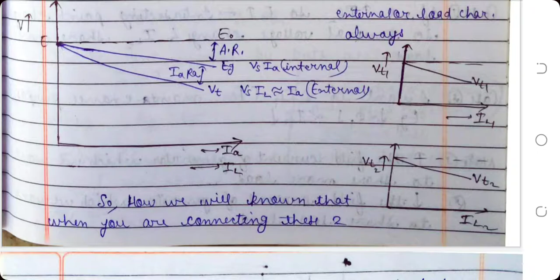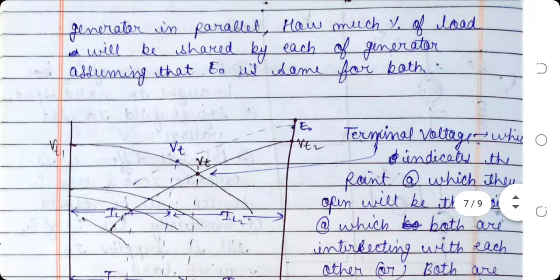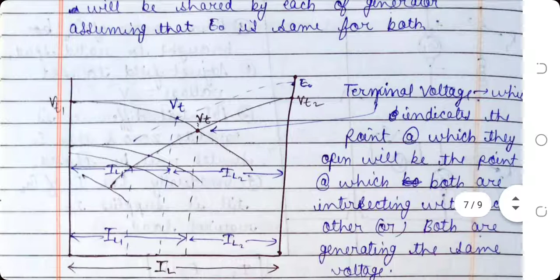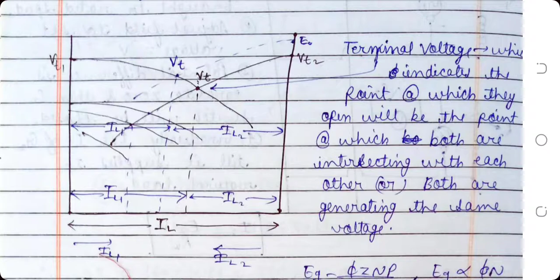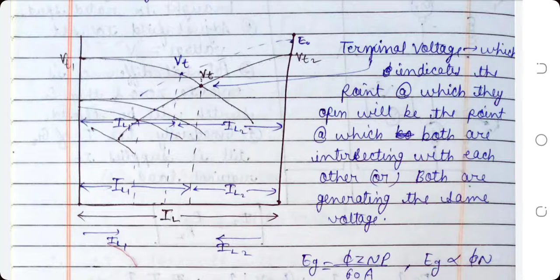So how will we know, when you are connecting these two generators in parallel, how much percentage of load will be shared by each generator, assuming that E0 is the same for both? So this is the diagram between voltage and load current. The terminal voltage is the point at which both characteristics intersect, where both are generating the same voltage. In this diagram, Vt, which is in the center of the diagram, is the terminal voltage.